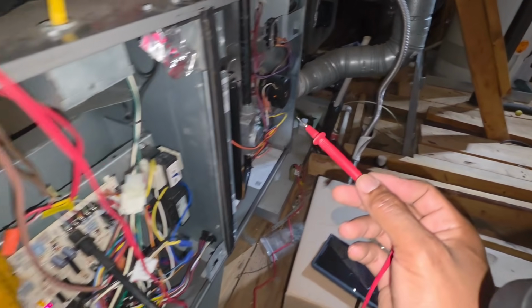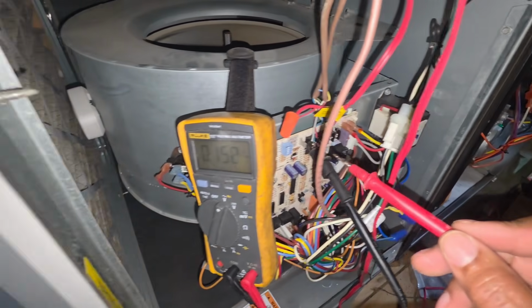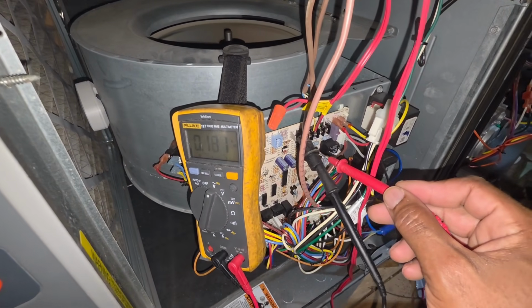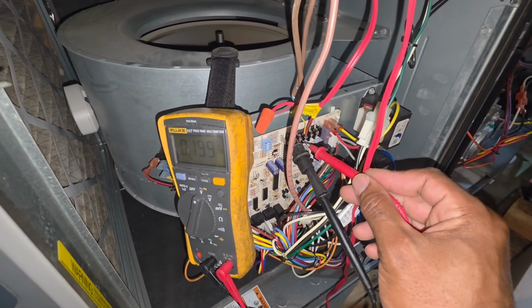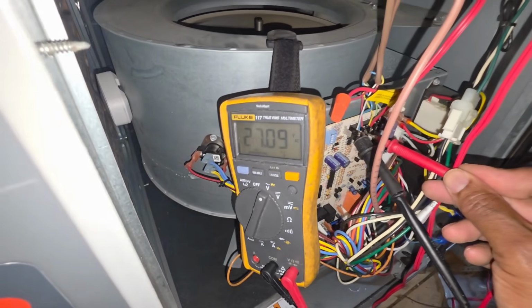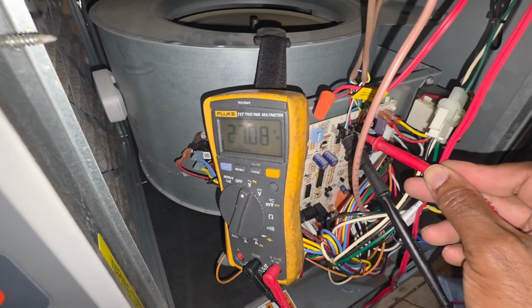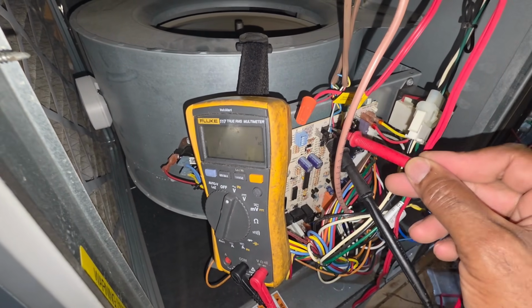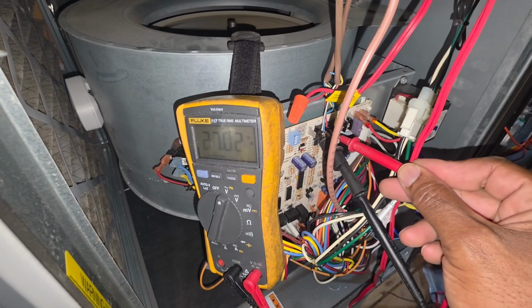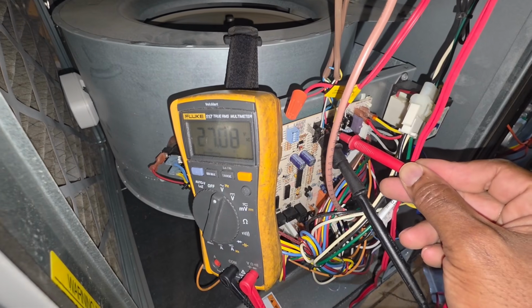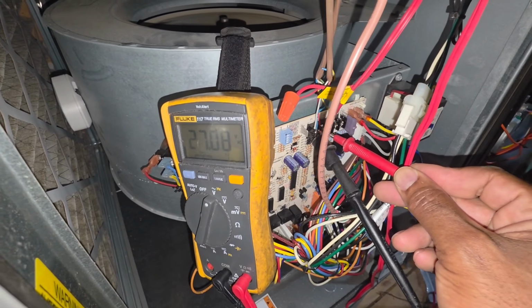Let's go back to this control board before we go over to the furnace section. So I got my probe on common. Let's go to red. I should be getting 24 volts, right? I got 24 on red. Basically, that's just my transformer sending 24 volts to the control board. That's another way to check your transformer.